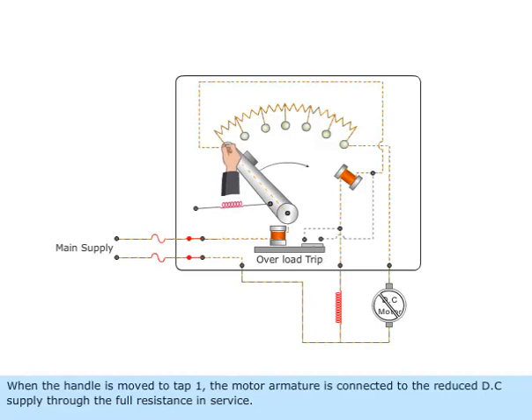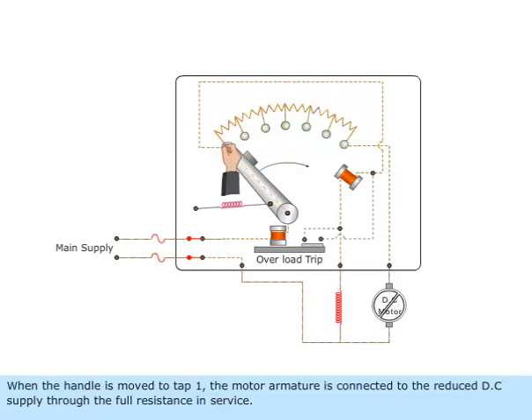When the handle is moved to tap 1, the motor armature is connected to the reduced DC supply through the full resistance in service. At the same time, the shunt field of the motor is also getting the full DC supply.